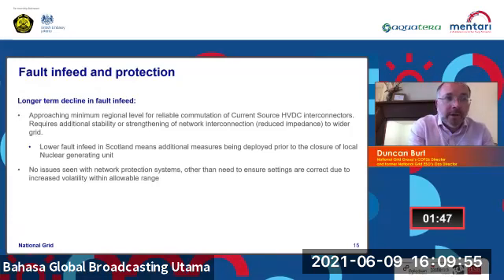We get a number of questions globally as to whether we've seen issues with network protection settings. I can confirm that in the UK, with either distance or unit protection, we've seen no issues with those protection systems as we've gone to lower inertia levels, other than the fact that they continue to operate within their safe range, but often at levels they haven't done before. We have occasionally found protection systems that tripped because the original settings at installation were done incorrectly, and therefore they're tripping incorrectly at operating levels they've not been at before. We send someone out to site, correct those levels to what they should have been established at originally, and those systems continue to operate fine.